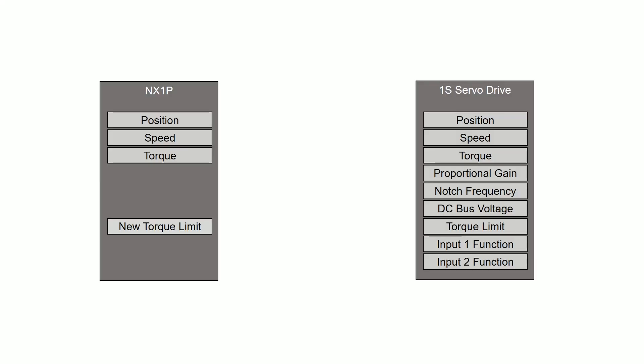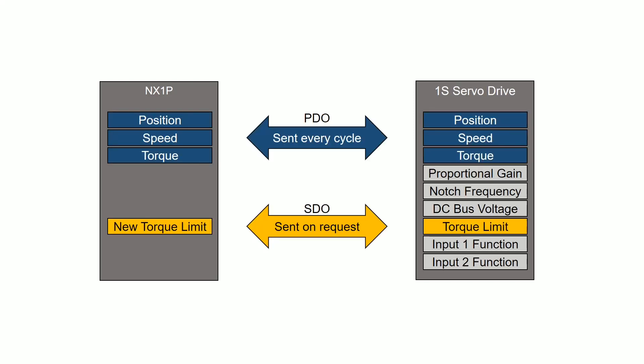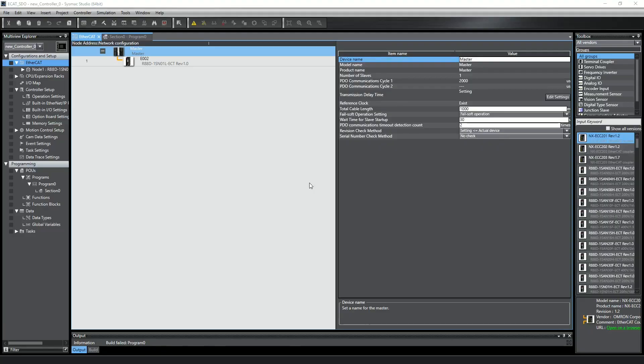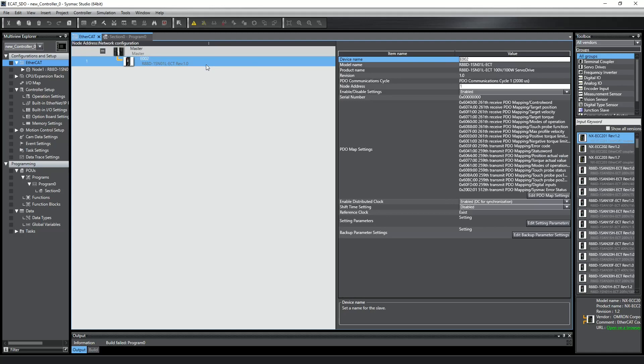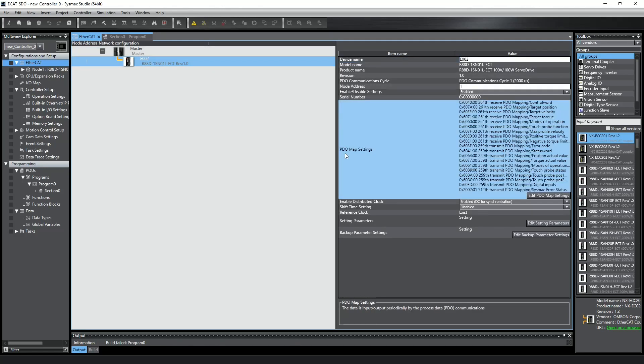Devices on the network have a number of parameters, known as objects, that can be accessed through EtherCAT. Some objects need to be updated every EtherCAT cycle, like commanded position or current velocity of a servo, whereas some are only accessed infrequently, like torque limits or position window settings. Objects that can be updated every EtherCAT cycle are known as process data objects, or PDOs.